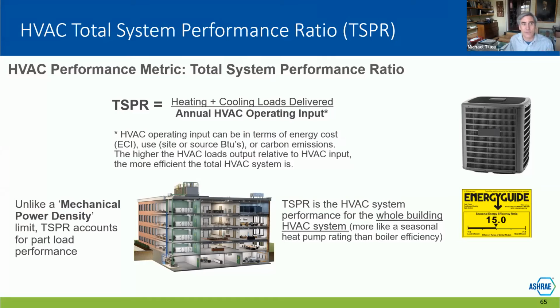The other interesting feature about the TSPR metric is we set it up, in case you haven't noticed, so that the input is on the denominator. So it's similar to a metric like COP or EER, where a more efficient design is going to have a higher TSPR value. That way it's aligned with the other HVAC metrics, so that as you see your TSPR get bigger and bigger, you know that your system is more efficient than your target.